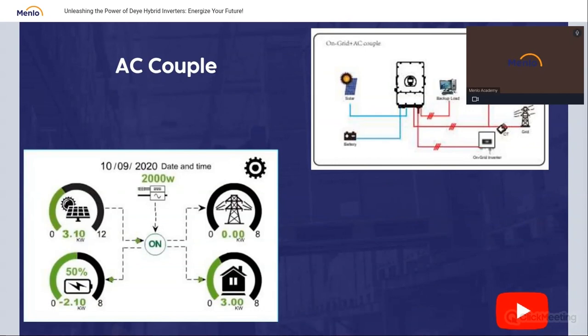Not with Deye. In Deye, you can connect an on-grid inverter to the gen input, set this input as an AC couple input, then the inverter simulates grid voltage and frequency, and turns on the grid inverter even when the grid is off. So you have an on-grid inverter—it might be microinverters, it might be SolarEdge—you might get some subsidies, and you cannot touch the existing installation otherwise. You have no way, unless you use Deye, because thanks to Deye, you can expand the existing installation with batteries, with full features, full abilities of a hybrid installation. You get not only increased self-consumption, but also endless backup energy as long as the sun is shining—for the next 5 trillion years, more or less.